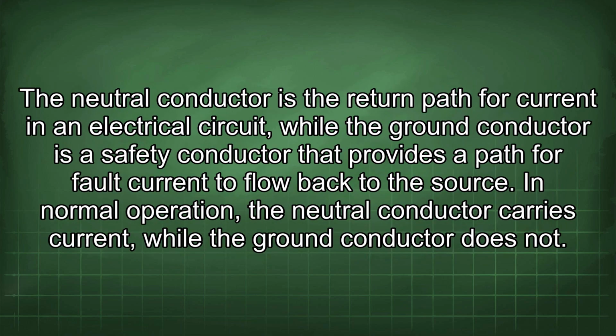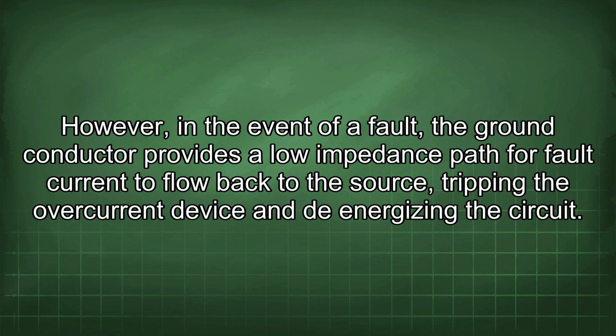The neutral conductor is the return path for current in an electrical circuit, while the ground conductor is a safety conductor that provides a path for fault current to flow back to the source. In normal operation, the neutral conductor carries current, while the ground conductor does not. However, in the event of a fault, the ground conductor provides a low impedance path for fault current to flow back to the source, tripping the overcurrent device and de-energizing the circuit.